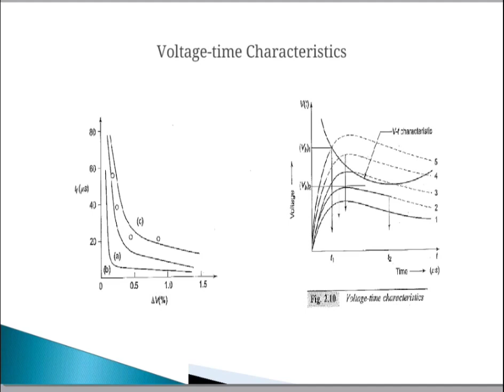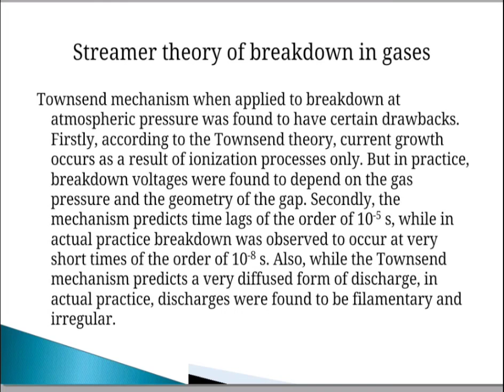Then we have to discuss the streamer theory of breakdown in gases. Townsend's mechanism, when applied to breakdown at atmospheric pressure, was found to have certain drawbacks. Firstly, according to Townsend's theory, current growth occurs as a result of ionization process only, but in practice, breakdown voltages were found to depend on the gas pressure and the geometry of the gap. Second, the mechanism predicts a time lag of the order of 10 raised to minus 5 second, while in actual practice breakdown was observed to occur in a very short time of the order of 10 raised to minus 8 second. Also, while Townsend's mechanism predicts a very diffused form of discharge, in actual practice discharges were found to be filamentary and irregular.